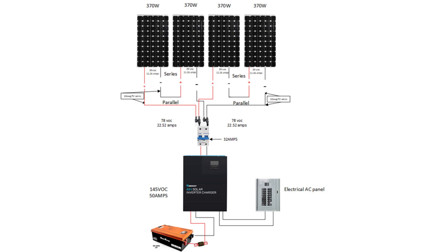The wiring back to the 32-amp breaker is more than sufficient to handle any shortage or surge — if there is a surge, the 32-amp breaker will trip. This is wired back to the inverter charge controller, which connects through a 100-amp fuse back to the 48-volt battery. There is a fuse or breaker between each of the devices for safety reasons. The inverter AC output is then wired into the AC electrical panel to power the cabin.